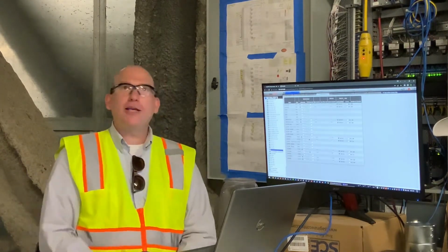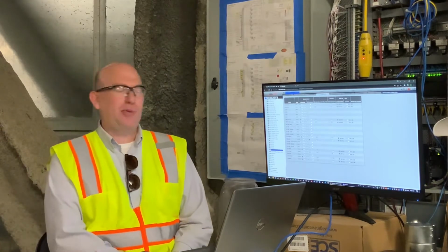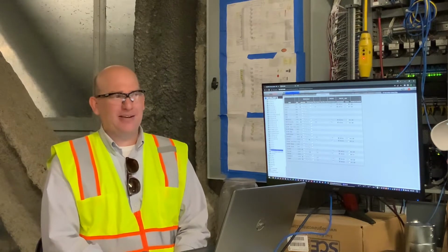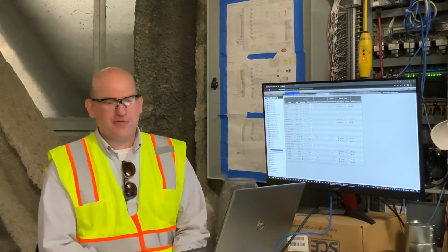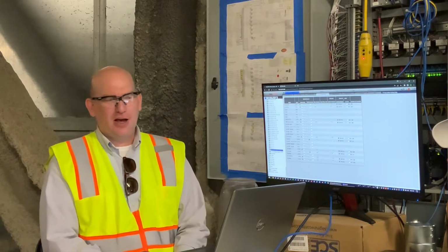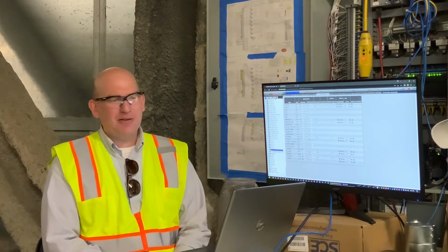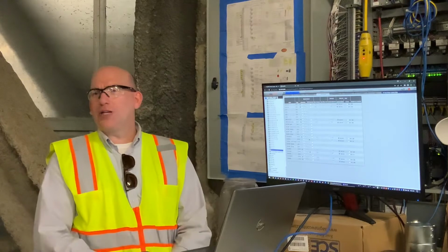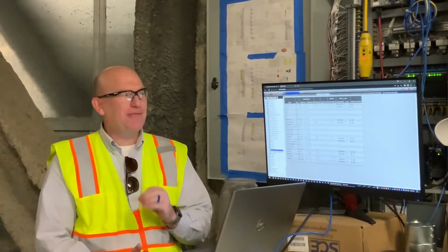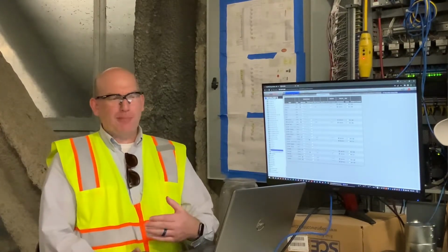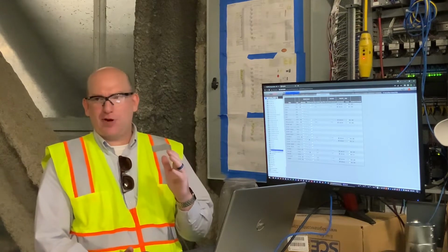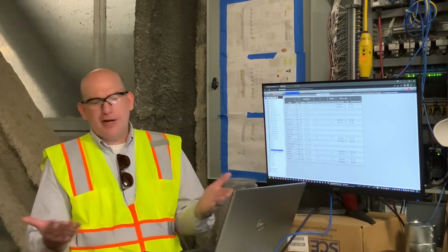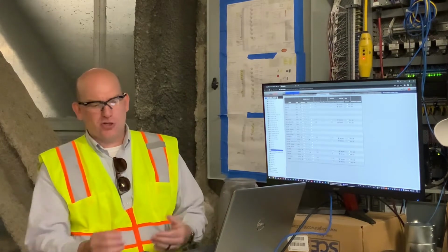So one of the ways you might use the trend sources tab would be, I'm having trouble with a room and the fan. I'm getting told that the fan for this fan coil unit is turning on and off, but it's happening inside of 5 minutes, okay? Generally, as a default, we take a sample every 5 minutes. So if this problem happens for 30 seconds and then the fan comes right back on, if that's in between those two samples, it might not work well, right? You might not be able to see it happening and diagnose the problem.